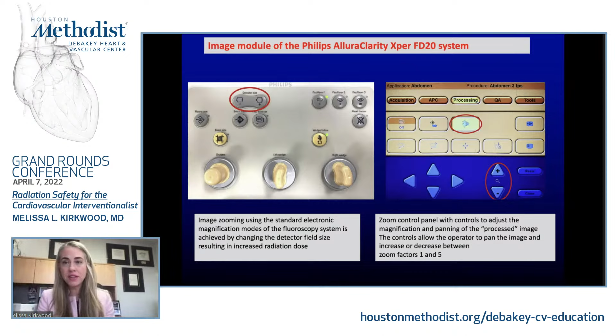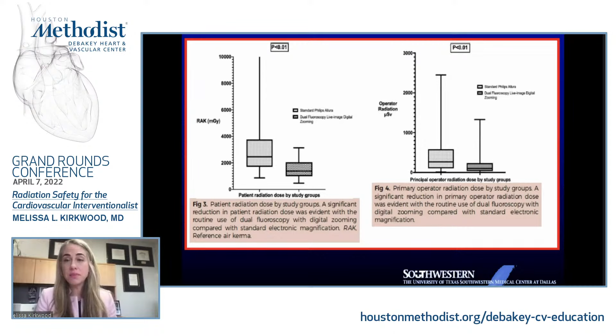And that doesn't change the dose at all. Now, it doesn't increase the spatial resolution. So the image is still a bit grainy, but it's larger. So if it's just that for us, sometimes our screen is kind of far from our eyes, if you just want the image bigger, the digital zoom is definitely the way to go. And when we looked at this, we saw that using just changing digital zoom compared to electronic mag definitely decreased the patient dose and the operator dose.